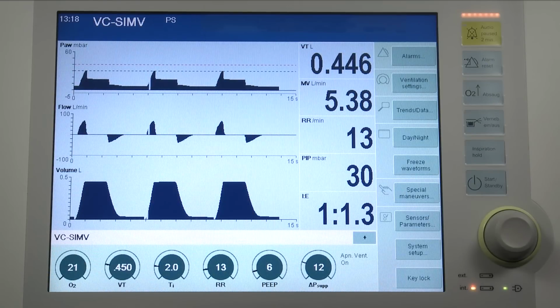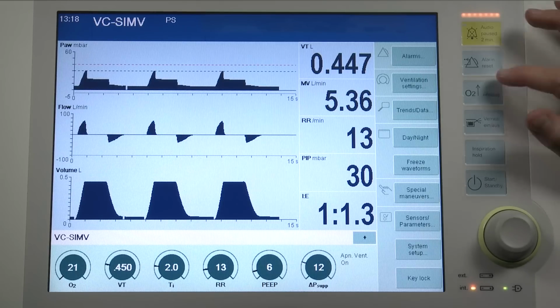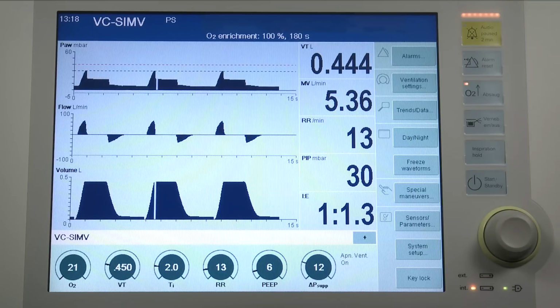To avoid any risk of hypoxia during endotracheal suction, Savina 300 offers a program for oxygen enrichment. During suction and for 2 minutes afterwards, the lower alarm limit for the minute volume is switched off. Press the O2 suction key. Savina 300 continues ventilating in the set ventilation mode at 100% O2. Within 180 seconds, Savina 300 expects a disconnection for suction.